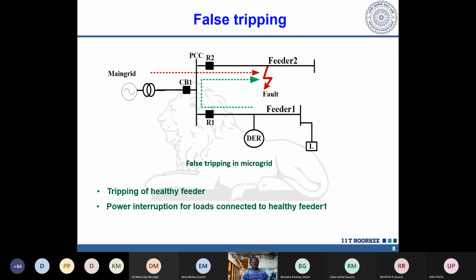Let us say one fault is incepted in feeder 2. So to this feeder 2, the fault current will be contributed by this DER as well as the grid side, both the sides, isn't it? Because these two are the sources present in this circuit. Now, this relay R2 is going to trip feeder 2, no doubt, because feeder 2 is the faulty feeder. However, feeder 1 is also going to be tripped, because R1 also will see some sort of high amount of current. So feeder 1 has no fault, but still it is going to be tripped, and this concept is known as false tripping.